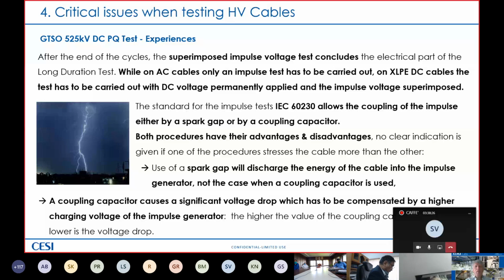Both procedures are quoted, but of course they have their own advantages and disadvantages. Unfortunately, so far, no clear indication is given if one of the procedures stresses the cable system more than the other. What we can tell you is that the use of a spark gap will discharge the energy of the cable into the impulse generator, and this is not the case when a coupling capacitor is used. A coupling capacitor causes a significant voltage drop, which has to be compensated by a higher charging voltage of the impulse generator. So the higher the value of the coupling capacitor, the lower the voltage drop. So in case you choose one of these two procedures, you have to take into consideration these situations.